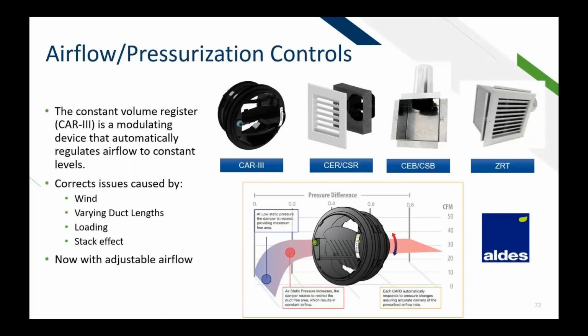Something else that you guys, I'm sure, are familiar with are the constant airflow regulators. This is from Aldes. It's a really great way to kind of auto balance. You don't need to balance. All you need to do is make sure that you have the correct pressure in the ductwork. As long as that pressure is within the range listed, you'll get a constant airflow. So right here, between 0.2 and 0.8 inches of water gauge, you get a 30 CFM. That's kind of what's shown right here. And then, of course, you can adjust that to whatever you need.